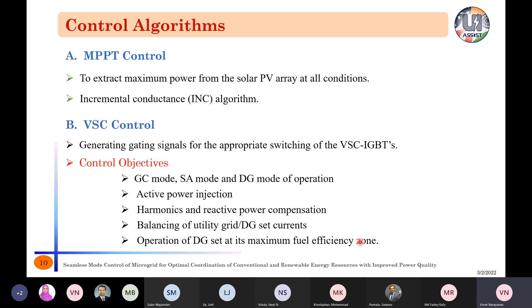And the main objectives of controlling the voltage source converter are that we have to operate the system in grid connected mode or in standalone mode or in DG mode of operation according to the system operating conditions. And then active power injection from DC sources, as well as power quality improvements such as compensation of harmonics, compensation of reactive power to realize sinusoidal and UPF grid currents or DG set currents, and then balancing of the supply currents, even though it is feeding unbalanced loads, then operation of DG set at its maximum fuel efficiency zone when the microgrid is synchronized into the DG set.